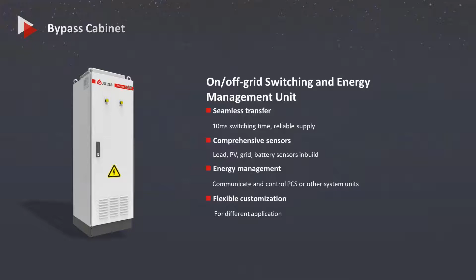The bypass cabinet would hit the spot. It can control the automatic switching time between off-grid and on-grid within 10 milliseconds. We can also understand that the main function of the bypass cabinet is to perform seamless transfer between on-grid and off-grid. So the AC terminal of the PCS will be connected to the PCS access port of the bypass. In addition, the bypass can also connect PV inverters, grid, generator, and load at the same time, providing customers with more flexible choices.